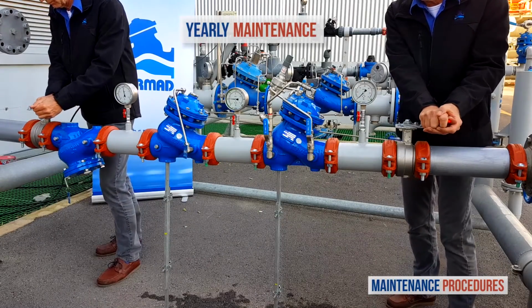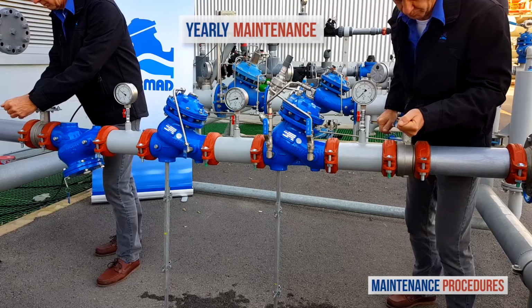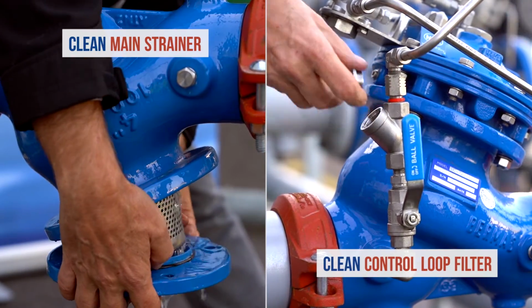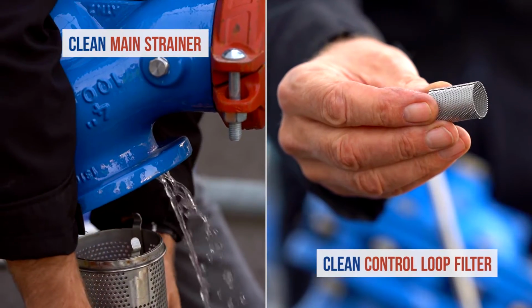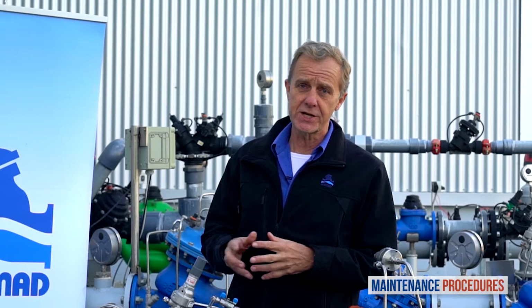Once a year, close both the upstream and downstream isolation valves and clean the main strainer and the valve control loop filter. Every 3 to 5 years, inspect the internal conditions of the pressure reducing valve.